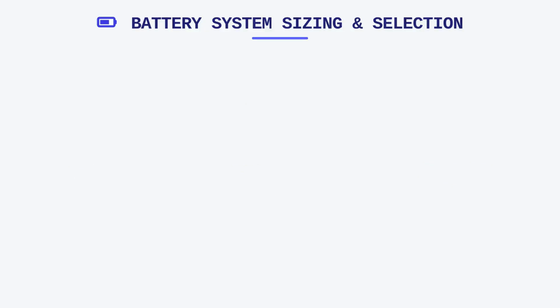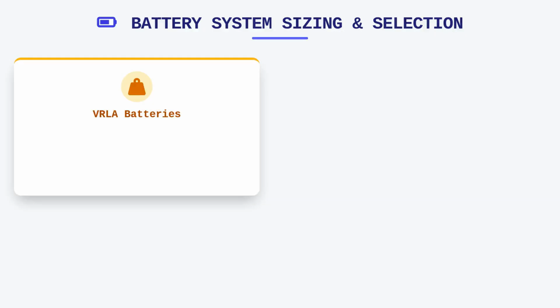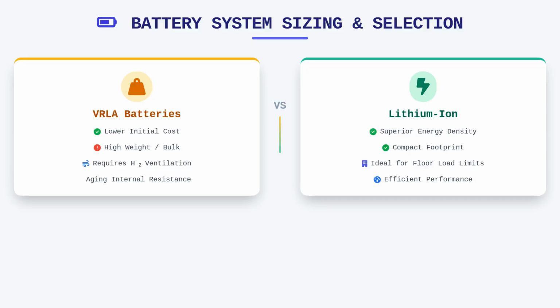Sizing battery systems requires a precise understanding of the load duration and the discharge characteristics of the chosen chemistry. Valve-regulated lead-acid batteries, or VRLA, are common due to their lower initial cost, but they are significantly heavier and require specific ventilation for hydrogen outgassing during charging cycles.